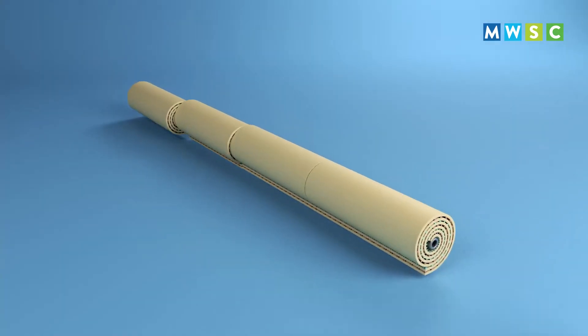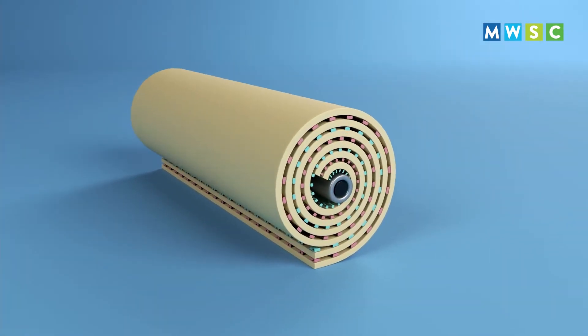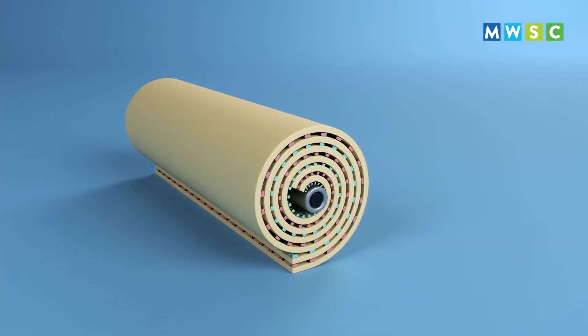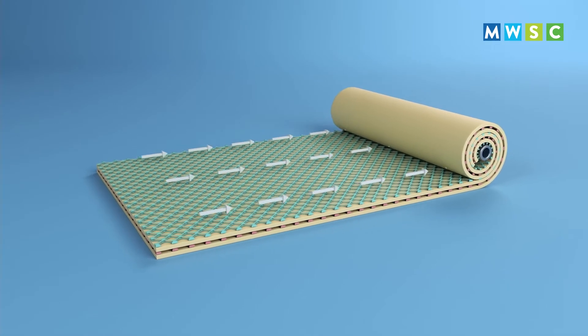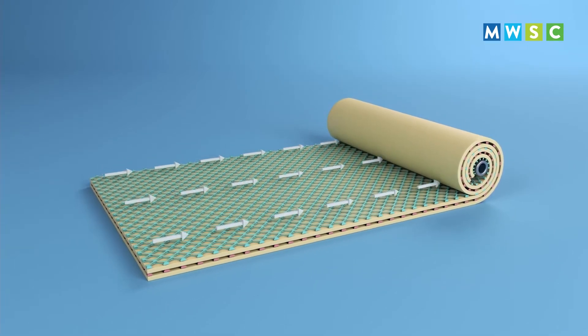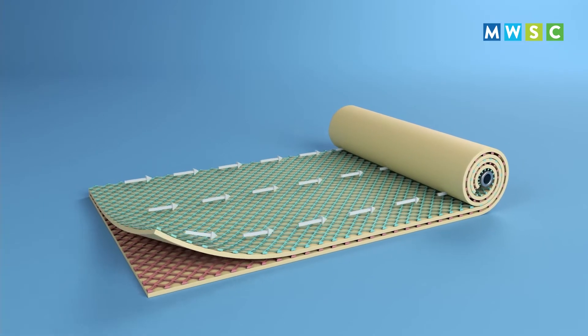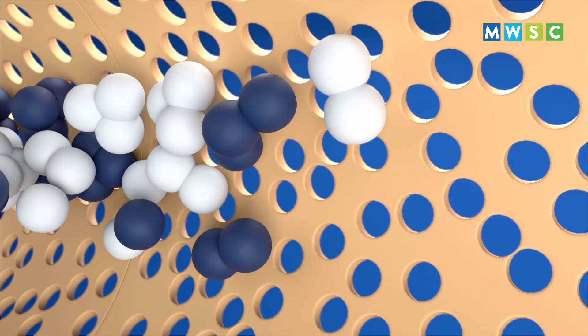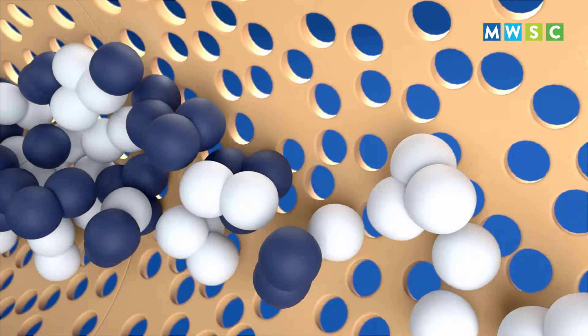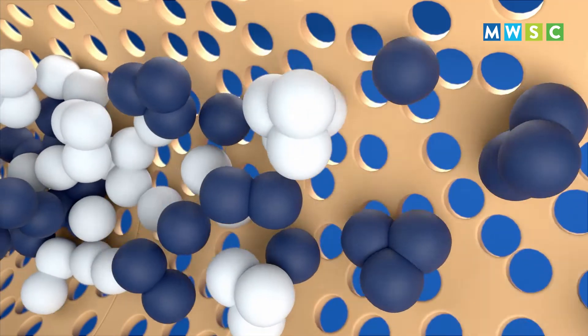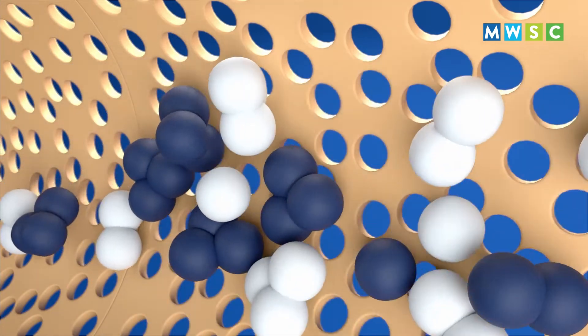Inside these pressure vessels, the source water is fed through spiral wound membranes. These membranes act like filters and prevent salt ions from passing through, thus separating the salt from the source water. This is mainly because the salt ion molecules are comparatively larger than the water molecules, which prevents them from filtering through the membranes.